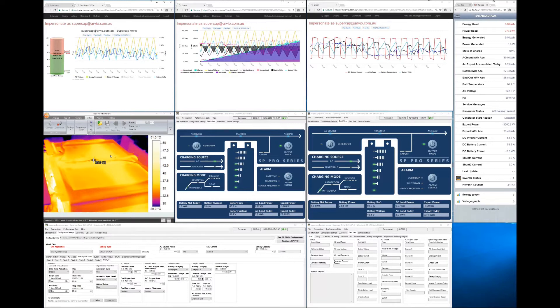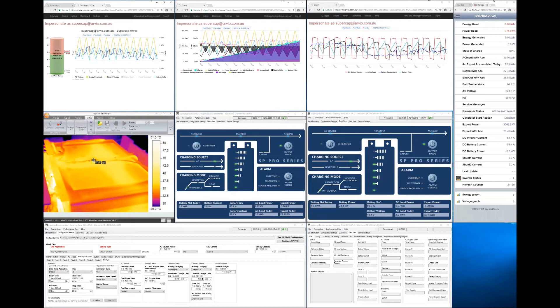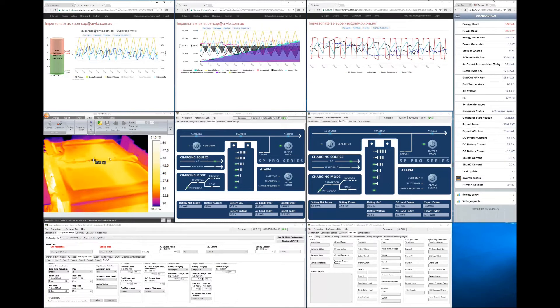This image here where the mouse is hovering over now is the thermal image from a Testo 885-1 thermal imaging camera. And we are now looking at the insides of the supercapacitor module. It's around 600 millimeters wide, 530 millimeters deep and 200 millimeters tall. And this temperature sensor is actually focused on the actual conductor, the main conductor coming from the positive terminal into the supercapacitor bank.